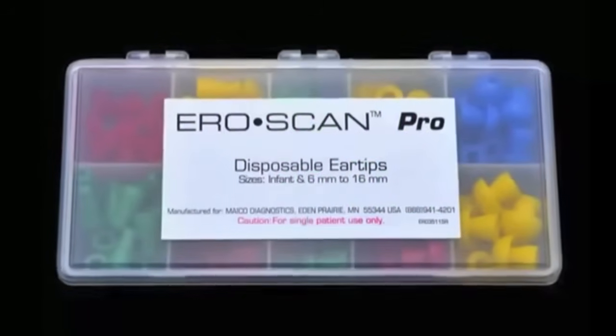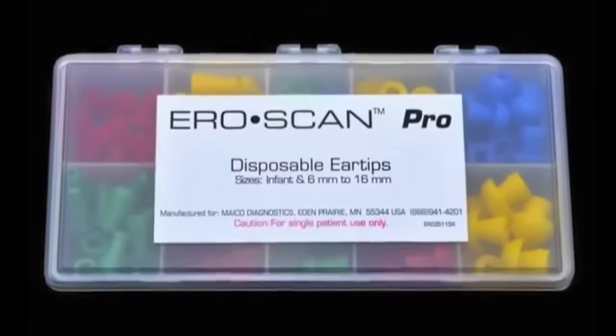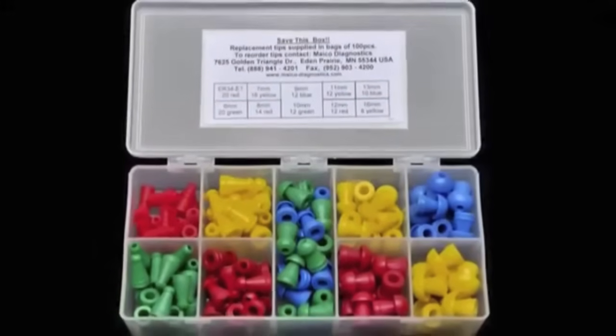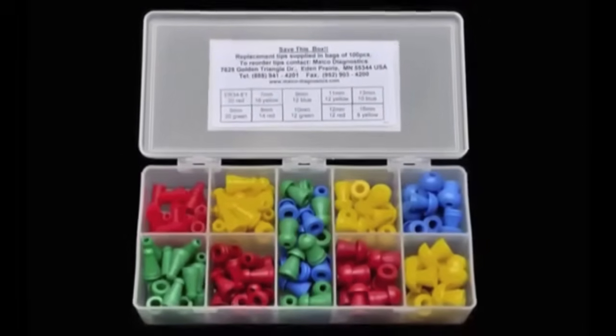Now we need to select an ear tip to insert over the probe tip. The Ero Scan Pro comes complete with a storage box that contains assorted sizes of disposable ear tips. These ear tips are color-coded for size. The proper ear tip will completely seal the ear canal and should be inserted gently, deep into the ear canal opening. The fit should be secure enough so that the probe will remain in the ear canal even with a light tug on the probe. If you're unfamiliar with OAE testing, please seek someone with proper training and experience to select the appropriate ear tip size and perform the probe insertion.